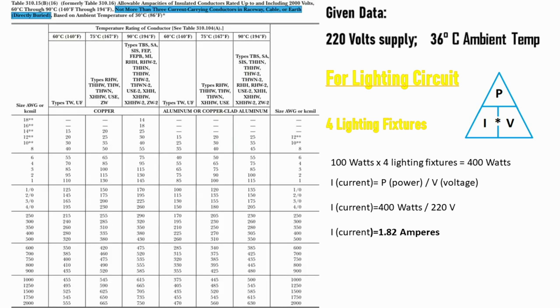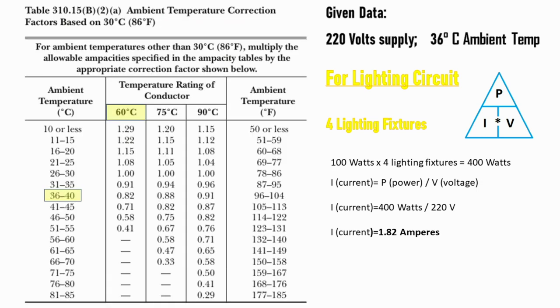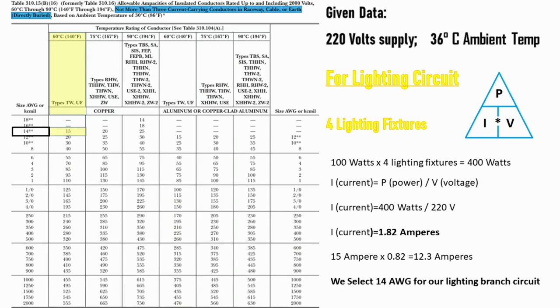From the table, we select the 60°C conductor temperature rating — moisture-resistant thermoplastic conductor. 1.82 amperes fits within the 15-ampacity rating for 14 AWG wire. But with a 36°C ambient temperature, the correction factor is 0.82. So: 15 × 0.82 = 12.3 amperes. Thus, 14 AWG wire is still safe to use.